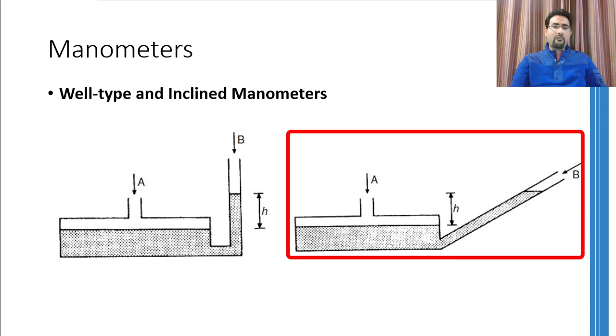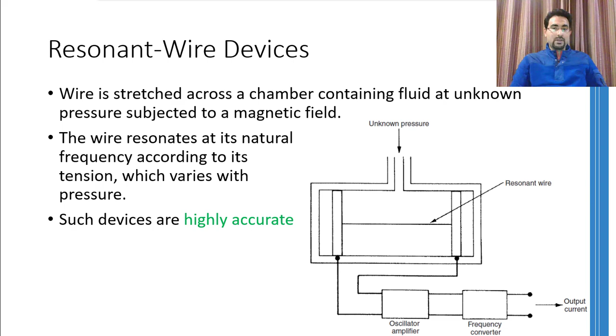The wire is stretched in a chamber that contains the fluid whose pressure is to be measured. The wire resonates at its natural frequency according to the tension which is produced in the wire. This tension is dependent on the pressure of the fluid in the chamber as well. So as the pressure changes, the tension in the wire changes and hence its natural frequency changes. Measurement of this natural frequency change can be related to the pressure change in the chamber.